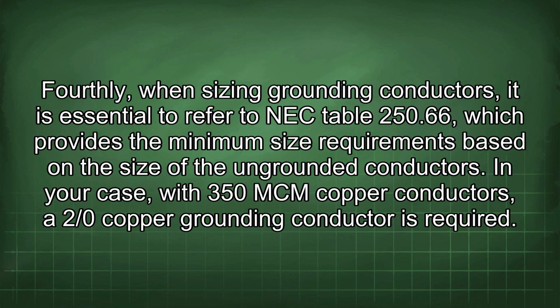Fourthly, when sizing grounding conductors, it is essential to refer to NEC Table 250.66, which provides the minimum size requirements based on the size of the ungrounded conductors. In your case, with 350 mcm copper conductors, a 2/0 copper grounding conductor is required.